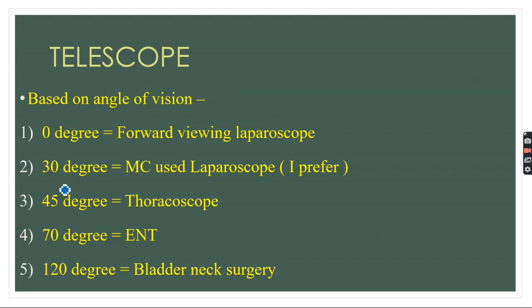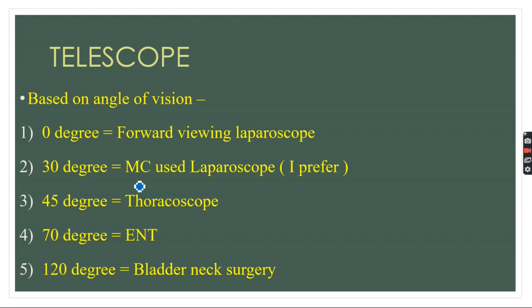Based on angle of vision, the telescope can be divided into: zero-degree (also known as forward-viewing or straight laparoscope), 30-degree (the most commonly used — preferred in most minimal access surgeries), 45-degree (commonly used as thoracoscope, with more range of movement), 70-degree (used in ENT endoscopy, including various diseases of the larynx), and 120-degree (used for bladder neck surgery).